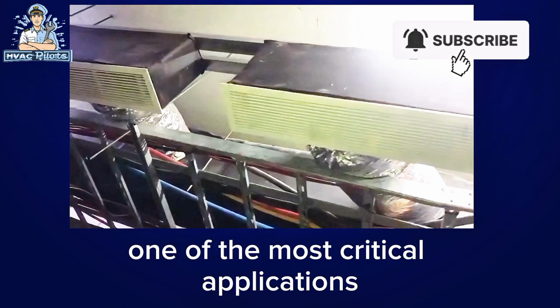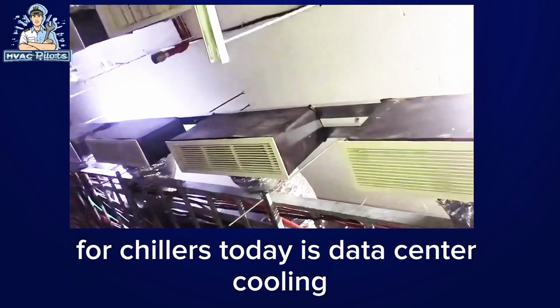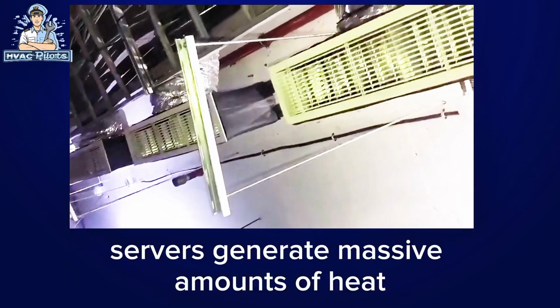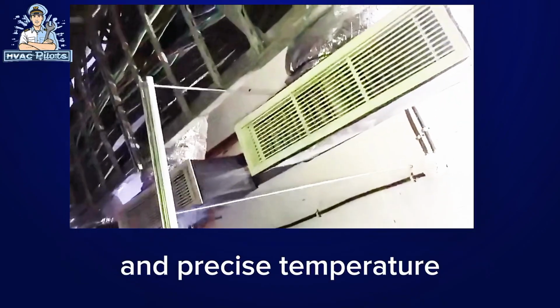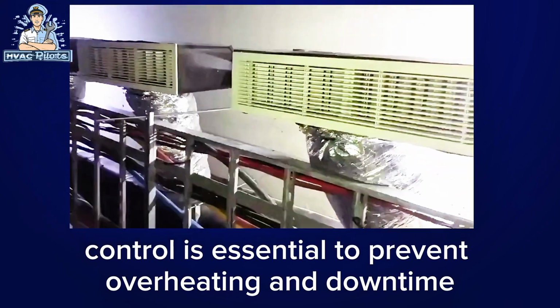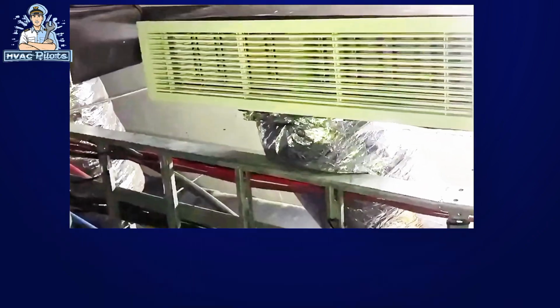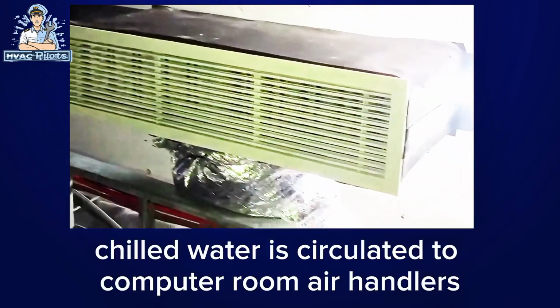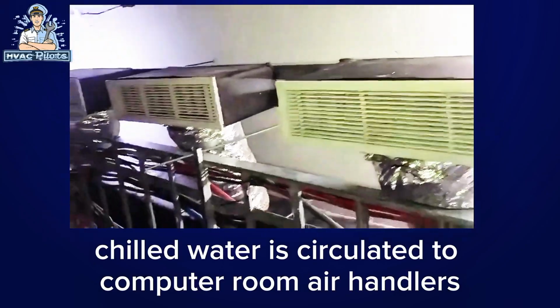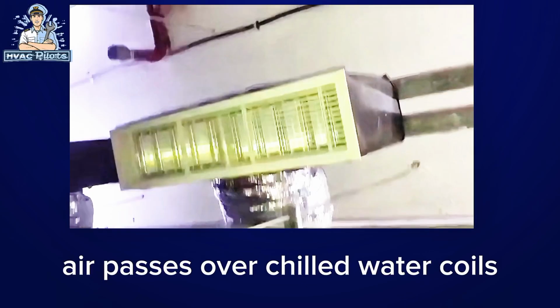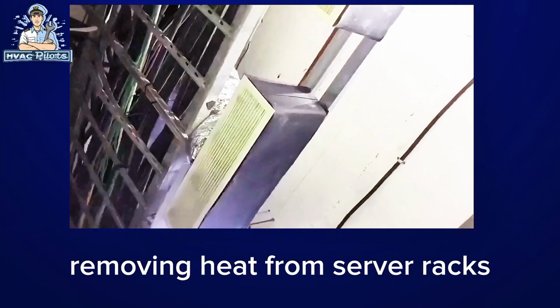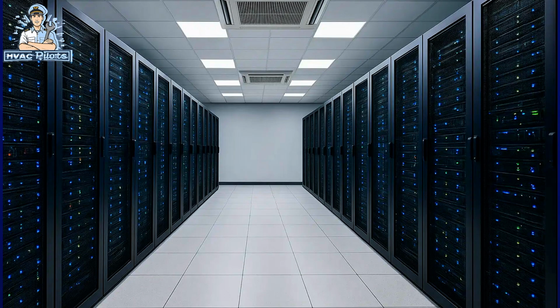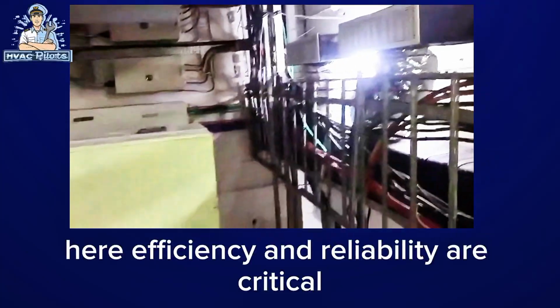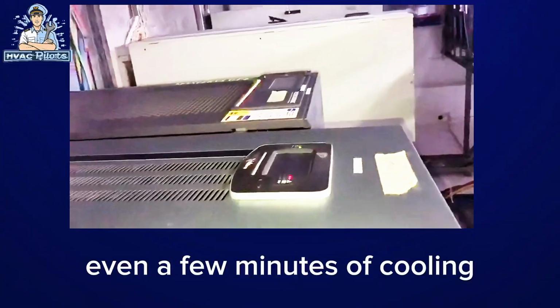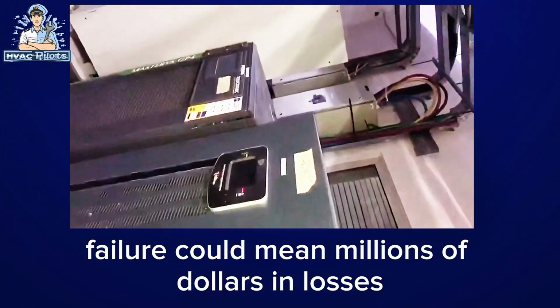One of the most critical applications for chillers today is data center cooling. Servers generate massive amounts of heat, and precise temperature control is essential to prevent overheating and downtime. In data centers, chilled water is circulated to computer room air handlers, CRAHs, or in-row cooling units. Air passes over chilled water coils, removing heat from server racks. Here, efficiency and reliability are critical. Even a few minutes of cooling failure could mean millions of dollars in losses.